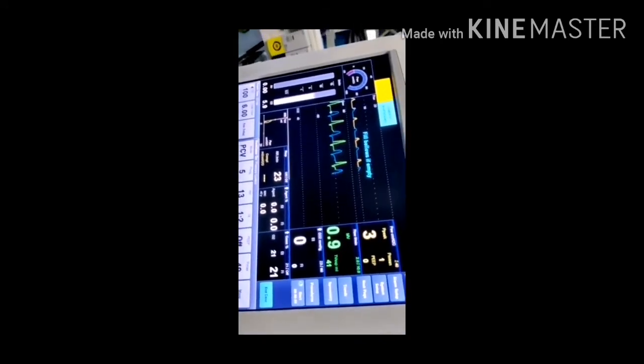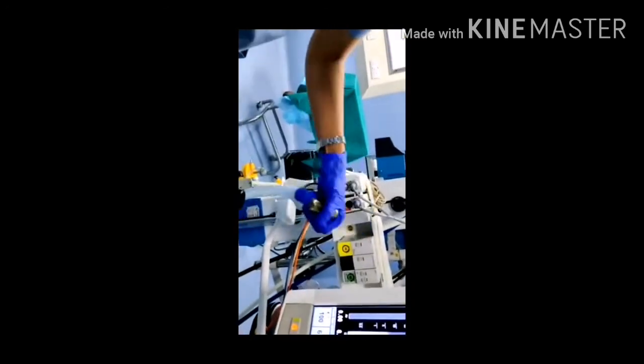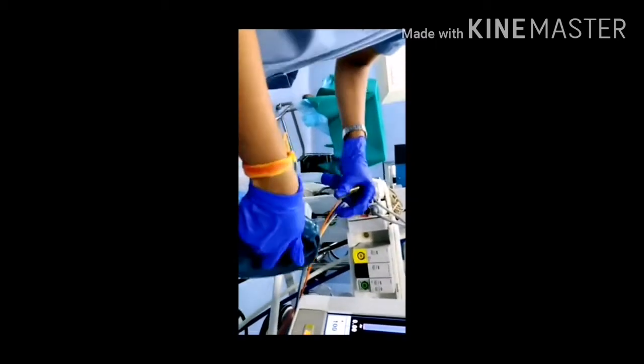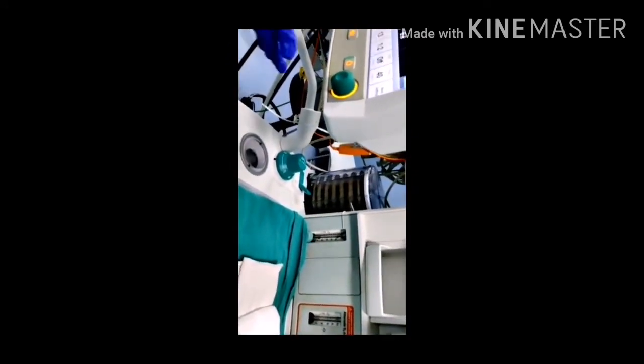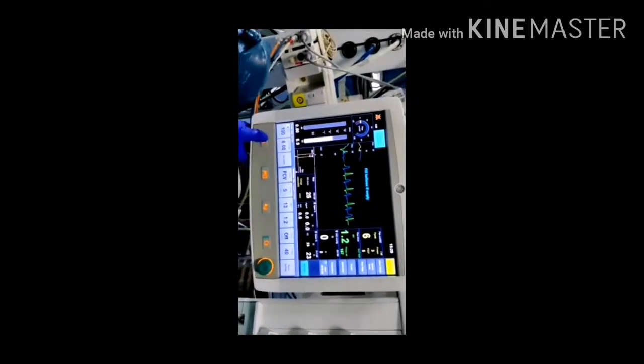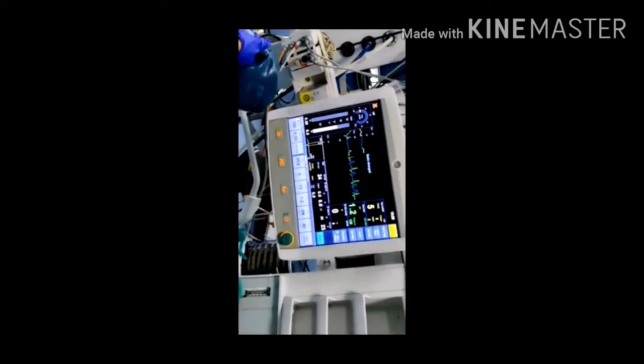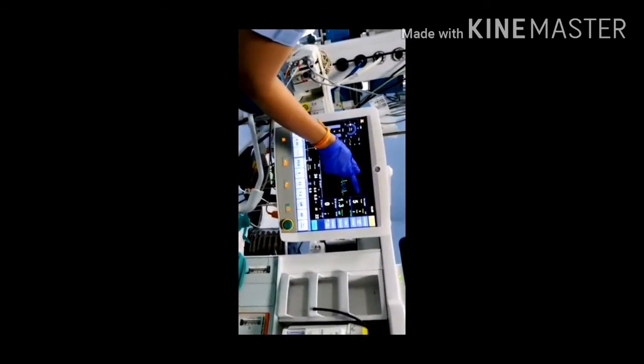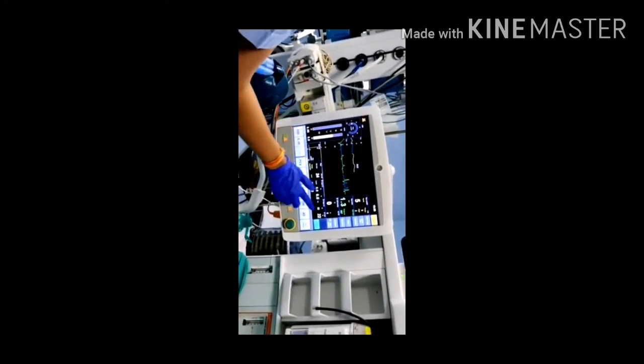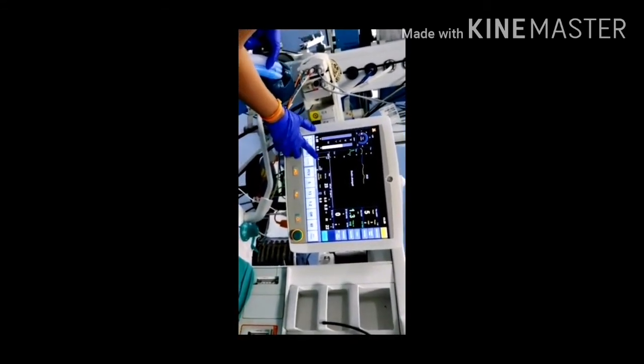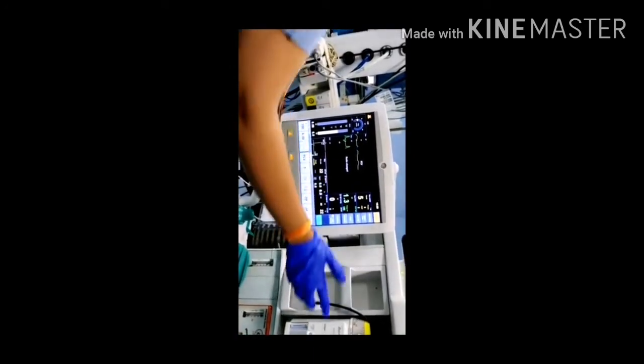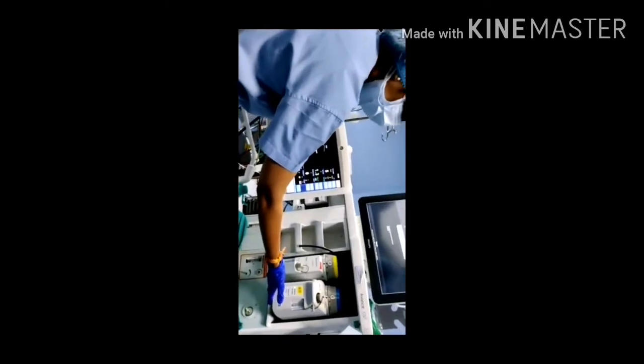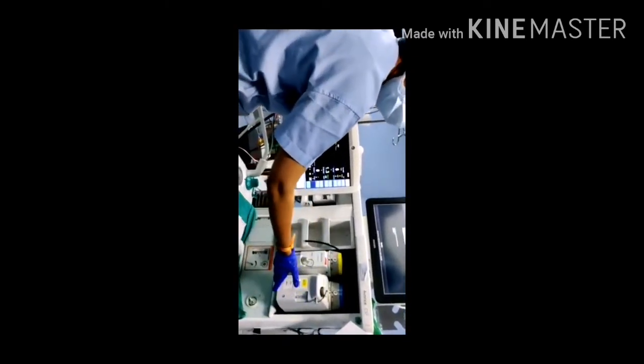Since the patient is not connected and we are using it on vent mode, we would be connecting a bag to the circuit, and since the bellows are collapsed, we will use the O2 flush, which would inflate the bellows. Here you can see the P peak achieved, flow, CO2 measurements, the gases that have been injected, the spirometry, the respiration rate, and the agent. The agents are sevoflurane and desflurane, which have been attached here. In case of leakages, you have to check this module as well, since if it is not locked properly, there would be leakage from the machine.